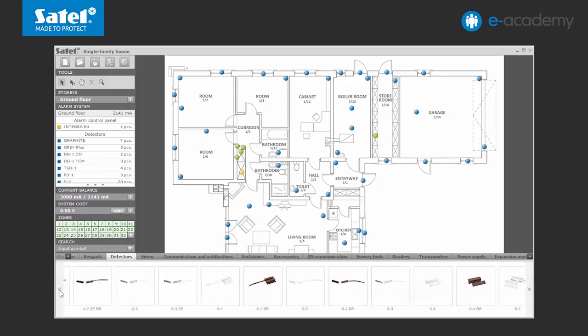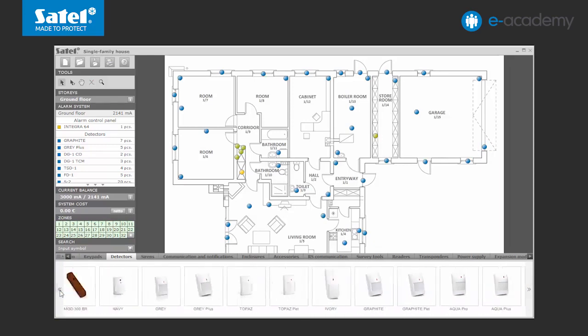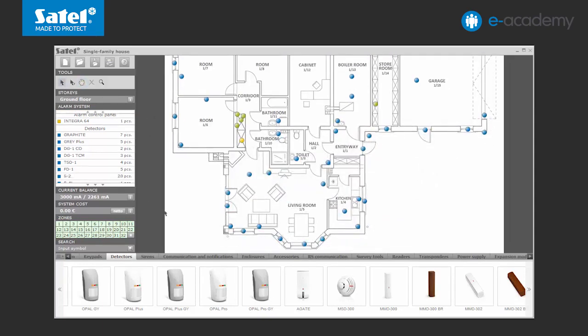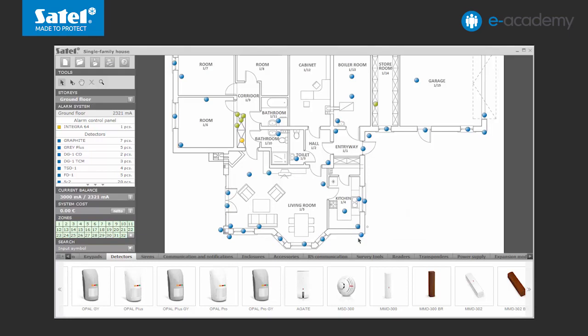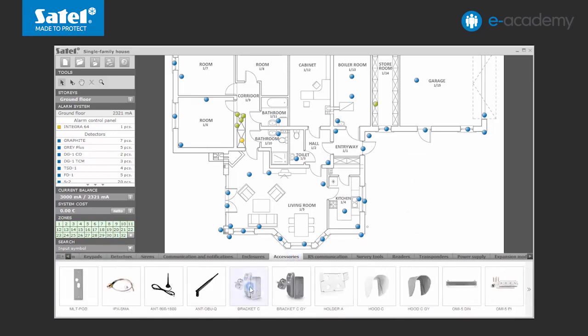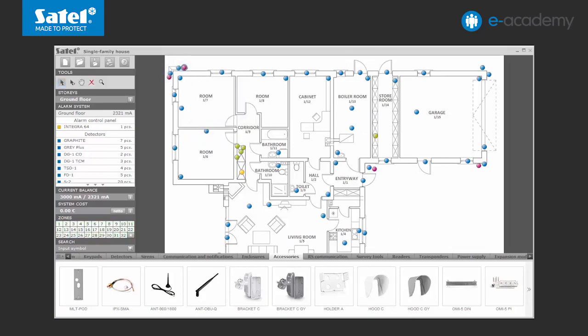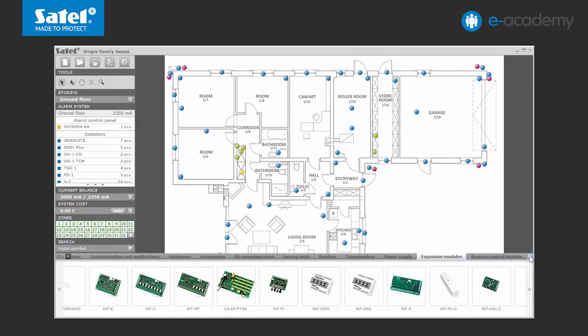Additionally, the perimeter protection will include dual technology OPAL PLUS detectors. To adjust the detector range ideally to the needs required, each detector will be mounted on an angle bracket from the bracket C set. In total, we have 56 detectors deployed in our premises. Now add the INT-RX-S expander to enable the system to be operated by using key fobs. Select from the list the T-4 key fob model you are interested in and determine how many key fobs you want to use.